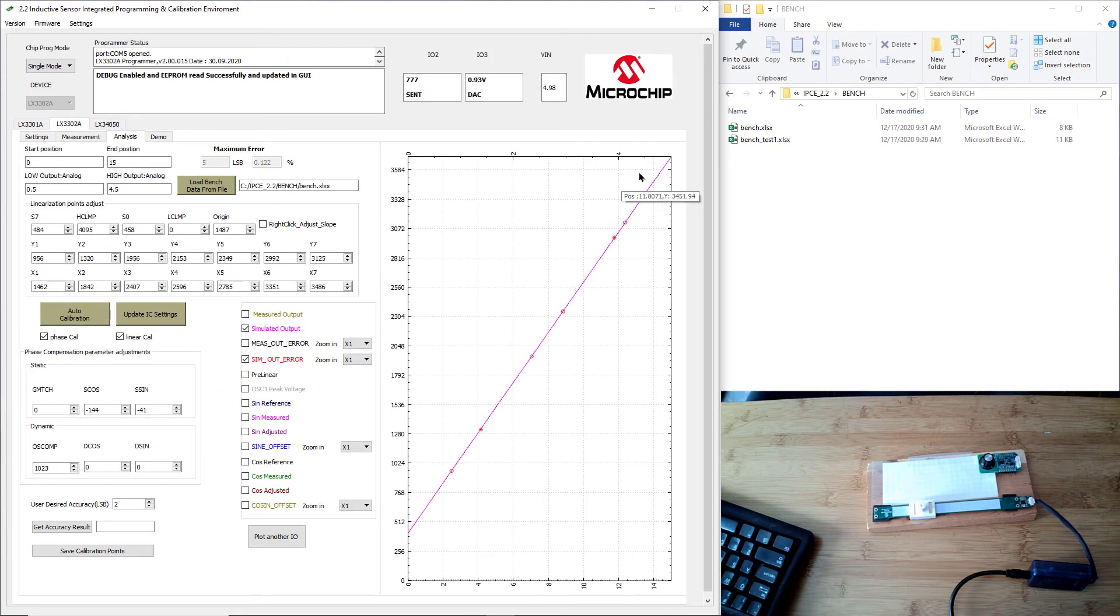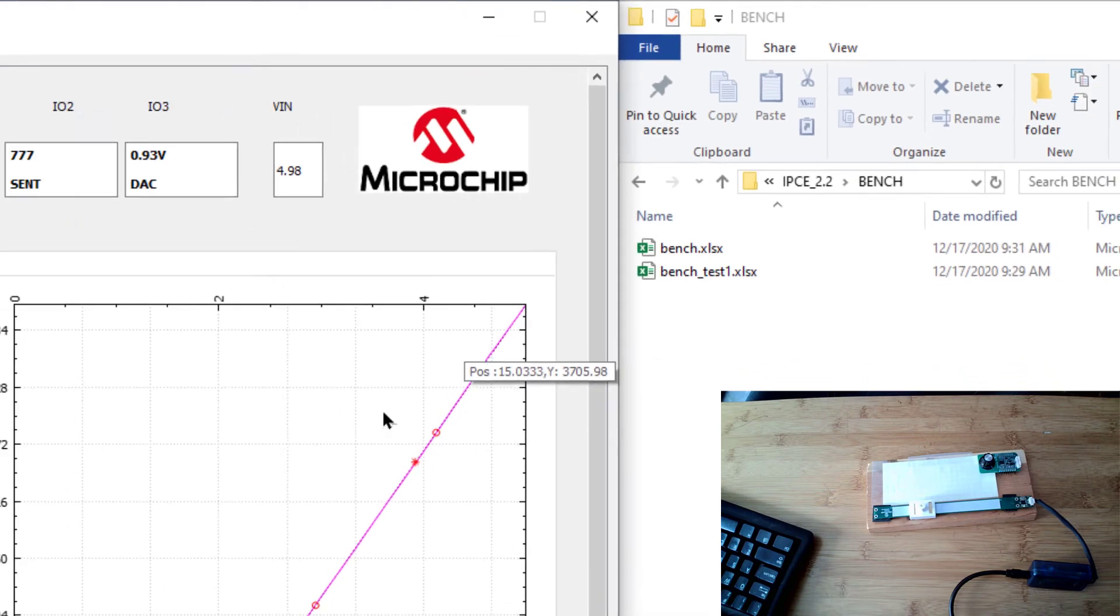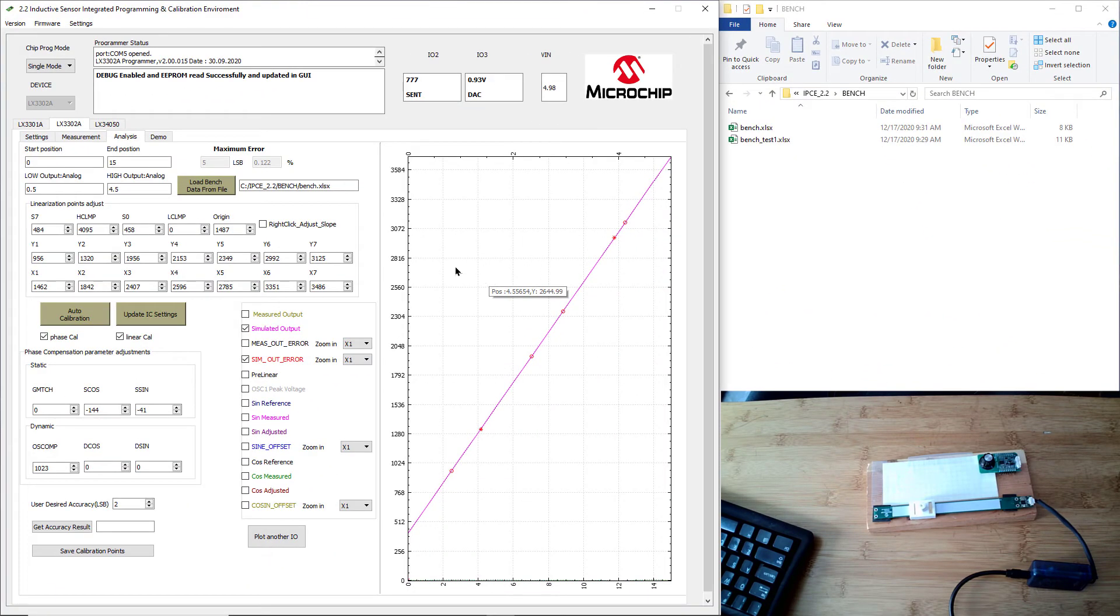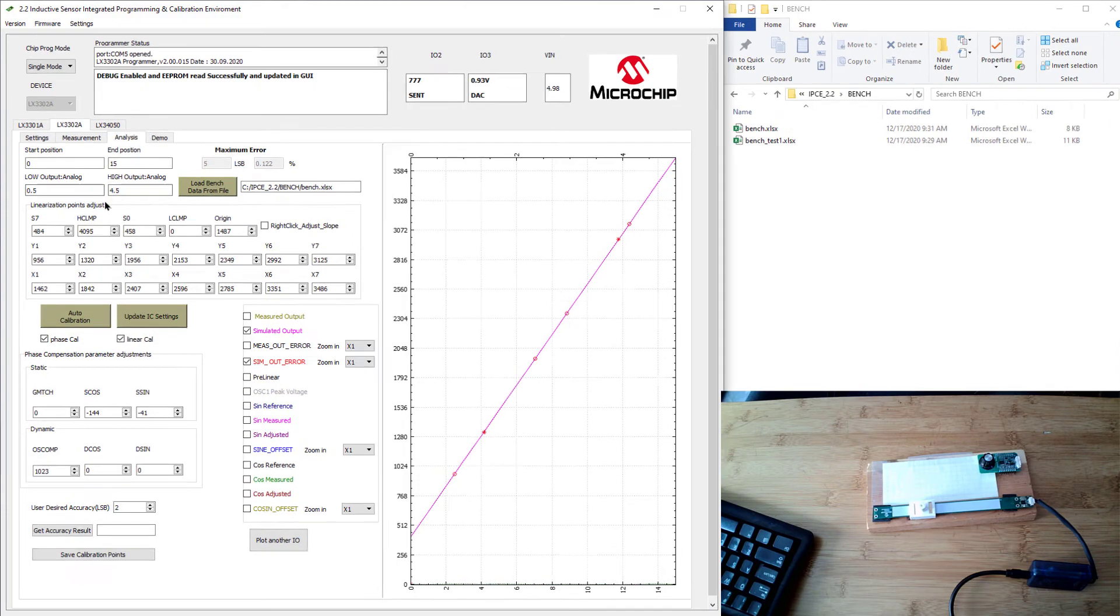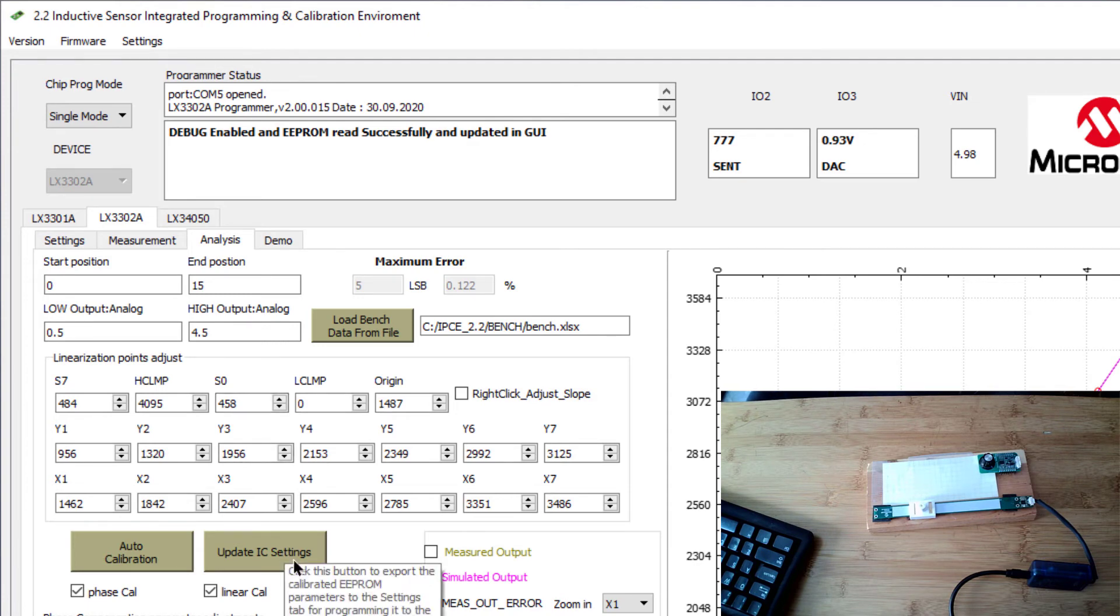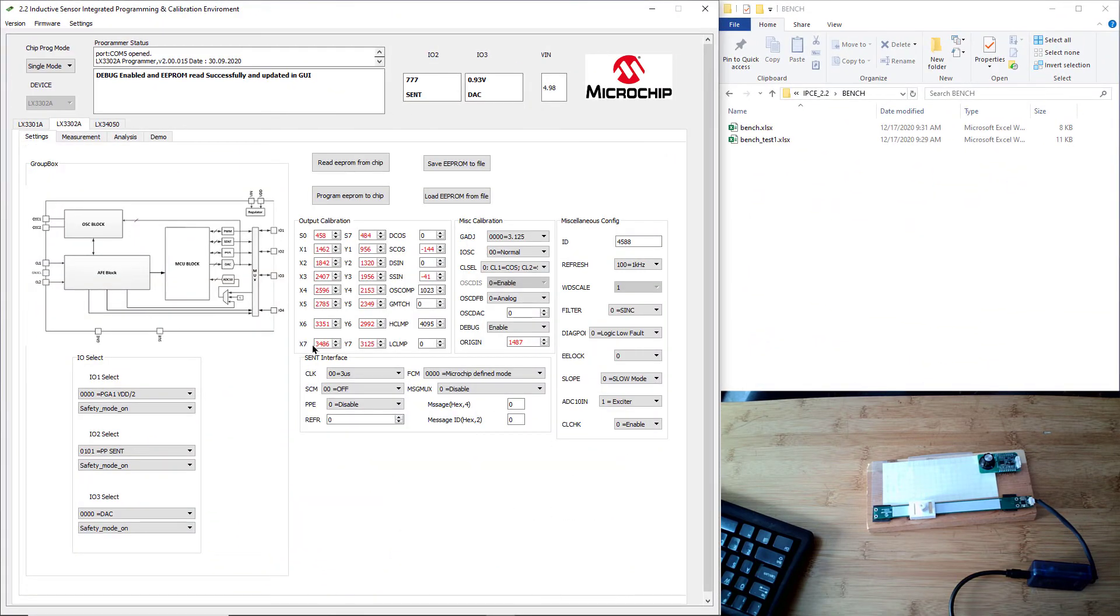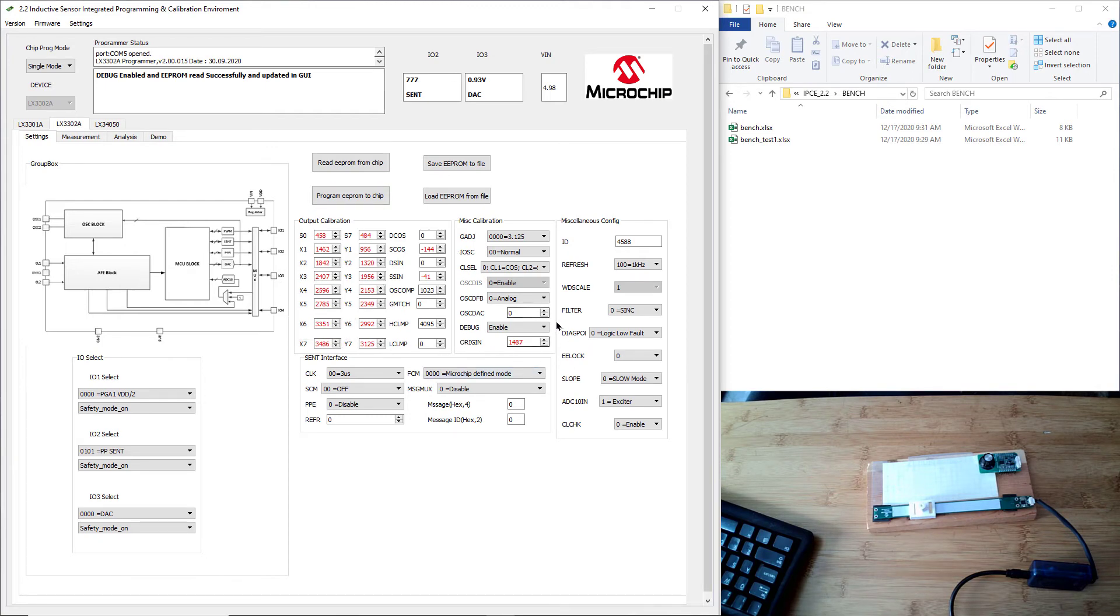And then the other one is 90% of 4095, which is up here, about right around 3696, and that represents 90%. In this case over here, 4.5 is 90% of 5 volts. So we're ready to go. We hit the update IC settings that brings it over to the settings page and takes all those calibration points. They've turned red in this location. You can see the origin got adjusted.